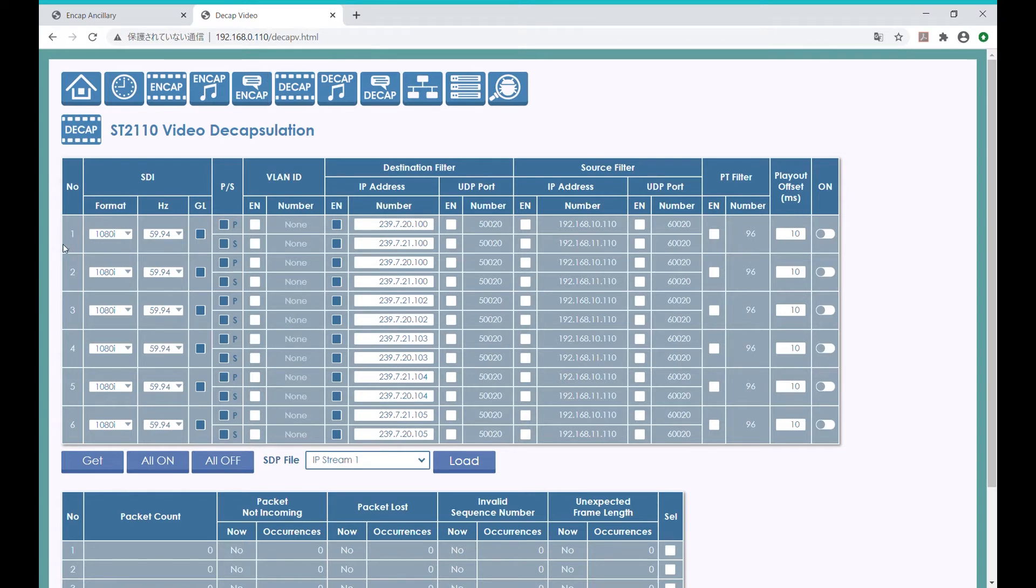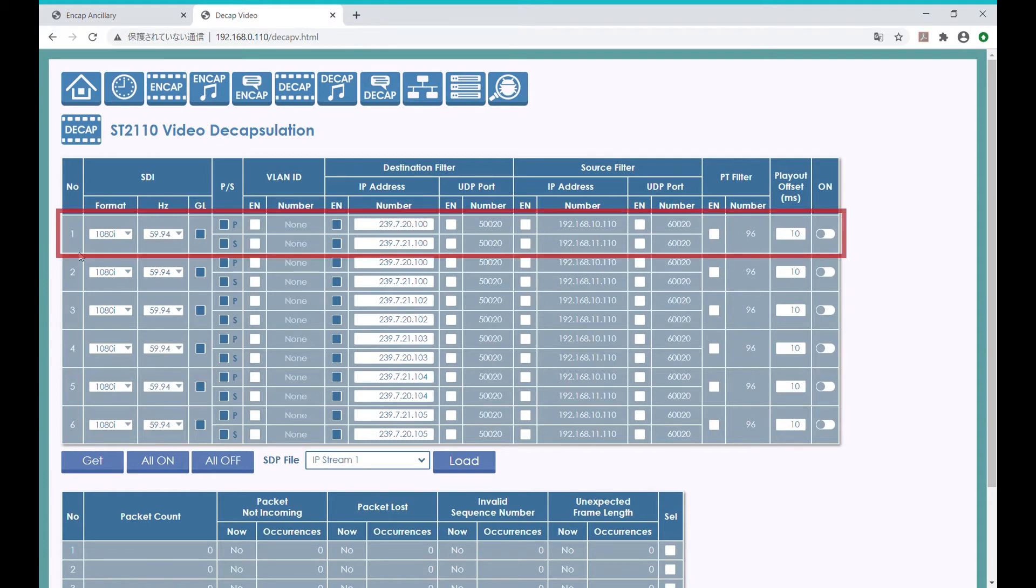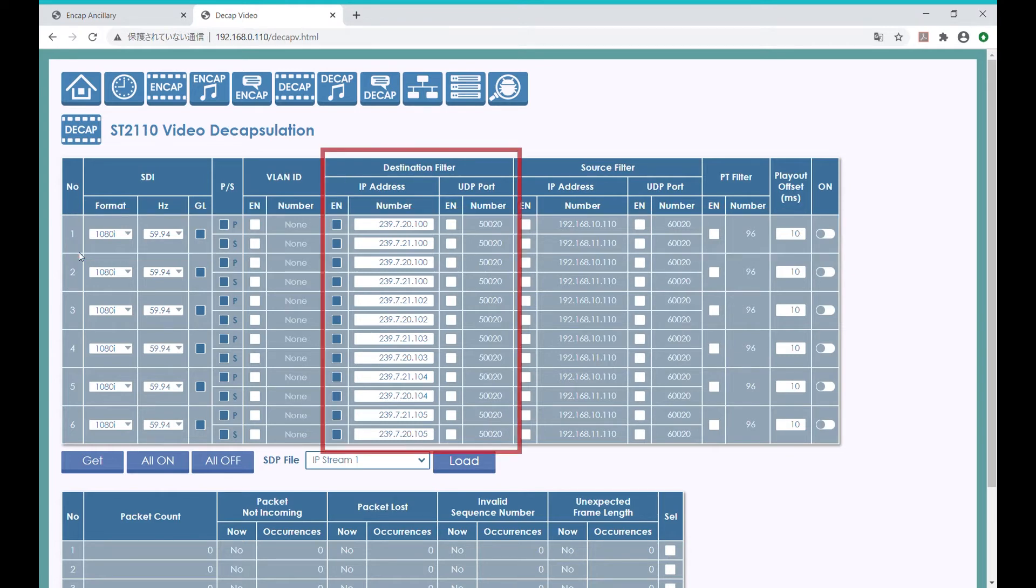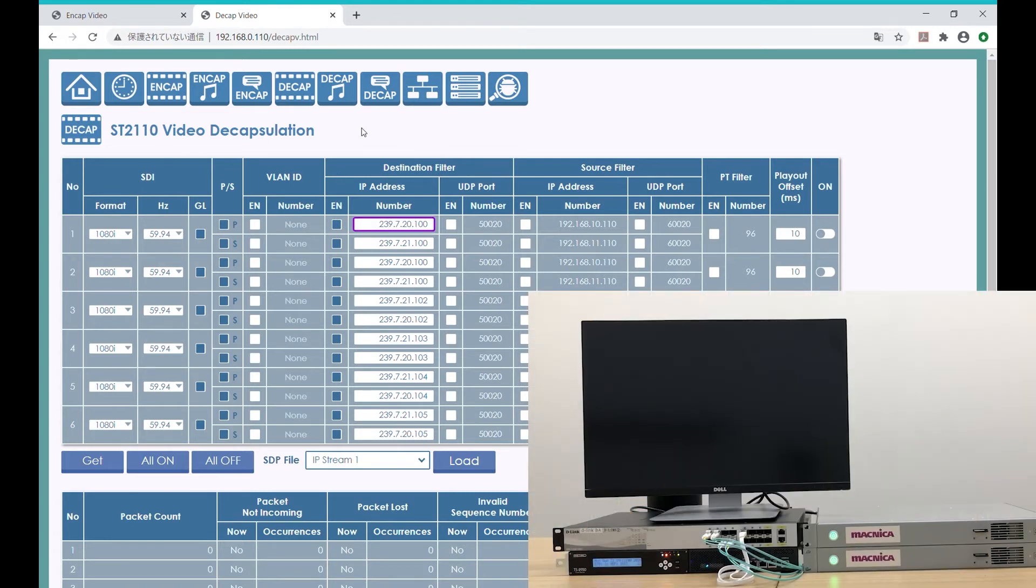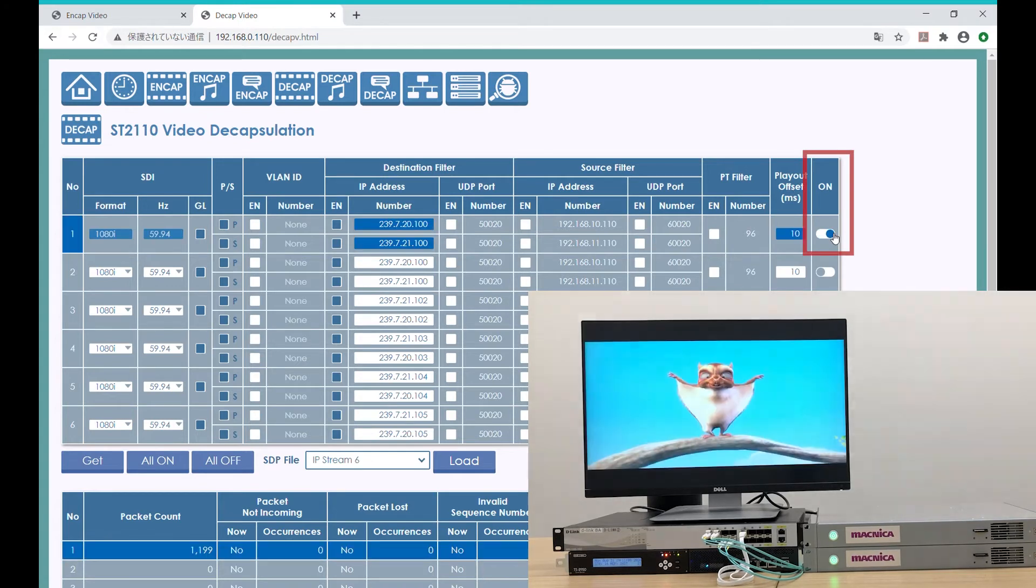Each of these represents the SDI output channel on the EVK. In this case, only channel 1 has the SDI cable connected. You can set the multicast address here. For this demo, we have already set the IP address to match the other side. Therefore, we can simply hit the button here to start receiving the IP stream.